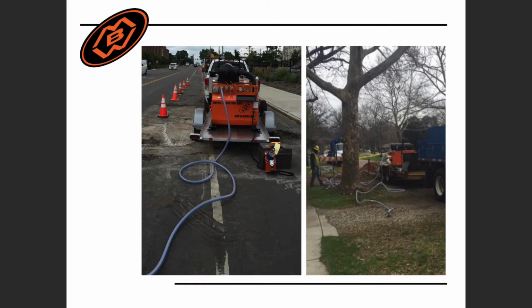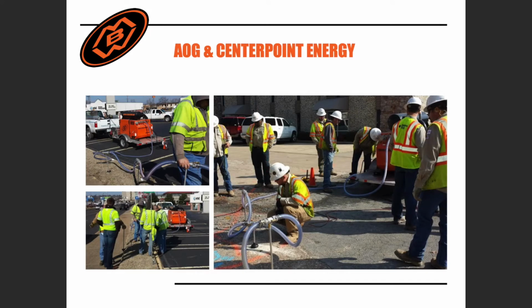We were able to pinpoint and locate the leak the day before the game, but the process would have been expedited if we had used 2 or more probe kits to cover a large area with this widespread migration of gas. Here's another set of pictures showing various setups for the VEU in action. As you can see, the probes are placed in the median on the upper right and then placed in bar holes in pavement on the bottom. The VEU probes can essentially be placed in any type of pavement or soil type. We need to just get below the cap that is preventing the gas from venting to atmosphere naturally.